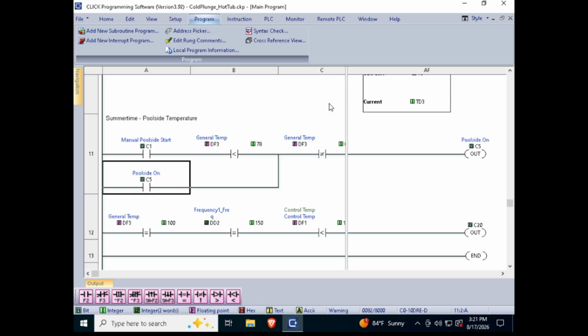So I'm going to attach the C5 bit to a heater, to our heater output rung, and that will actually turn on the heater, but this is just like a control rung. What that will do is turn on the heater all the way until it reaches 85. Once it reaches 85, it's going to unlatch this bit.